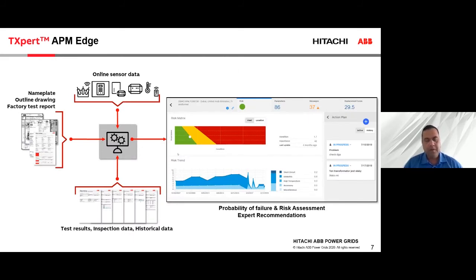Moving on, as I mentioned before, APM Edge will take not only test results, inspection data, historical data, and nameplate data. We also take into account online sensor data, such as online DGA, online PD, and moisture monitoring. All of that can now be fed into this APM Edge advanced analytical software. Then we run a lot of different kinds of algorithms, and we try to calculate the risk matrix and the risk trend, and we give you a score on whether the transformer is in the green zone, the medium risk zone, or the red zone. Depending on that, we also calculate whether we should be replacing this transformer or doing a maintenance activity on it.